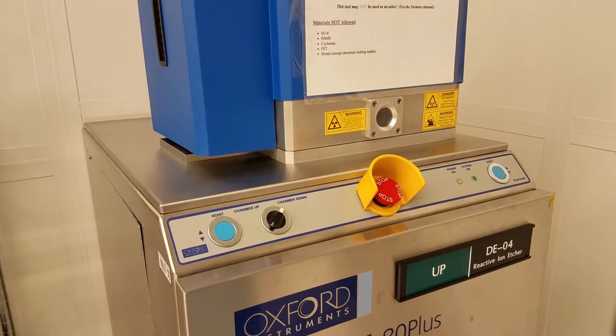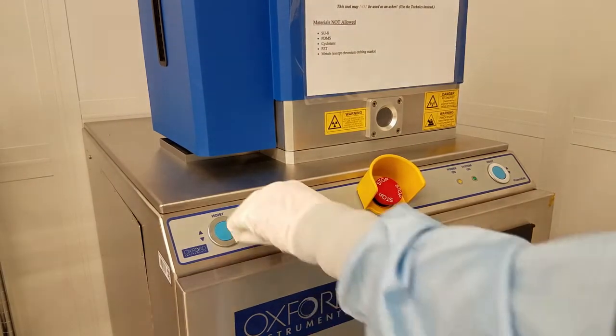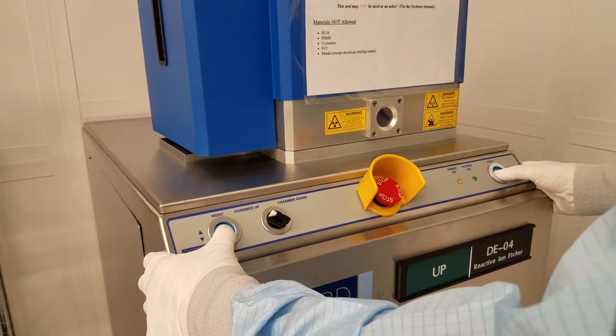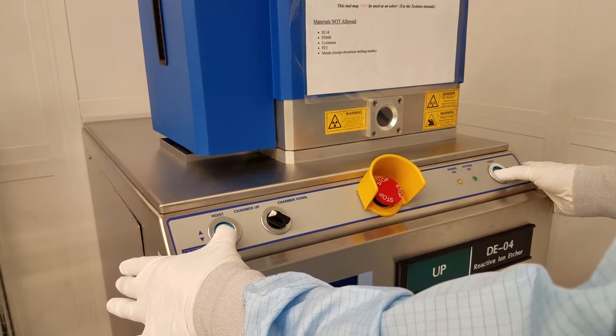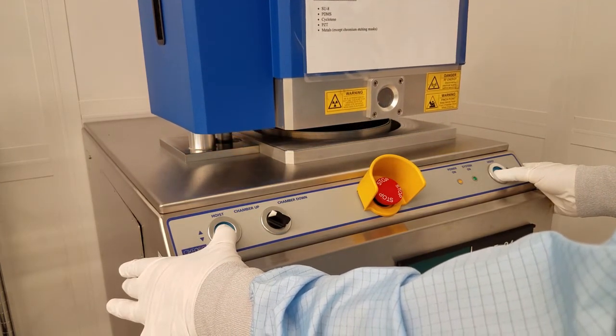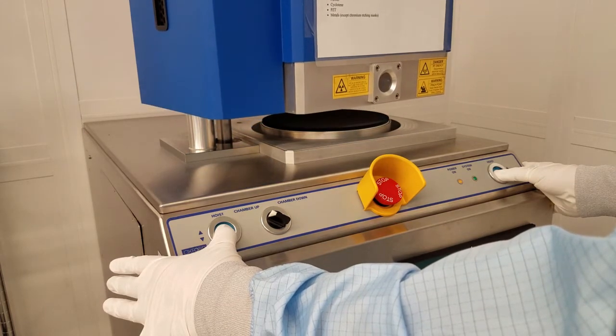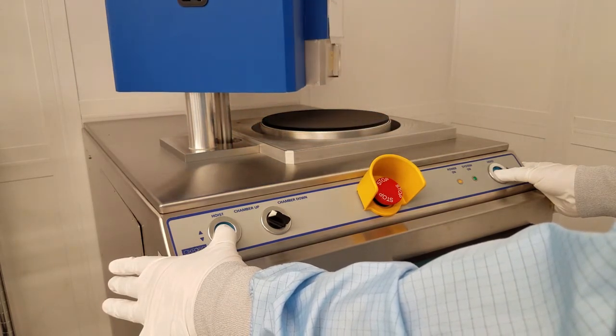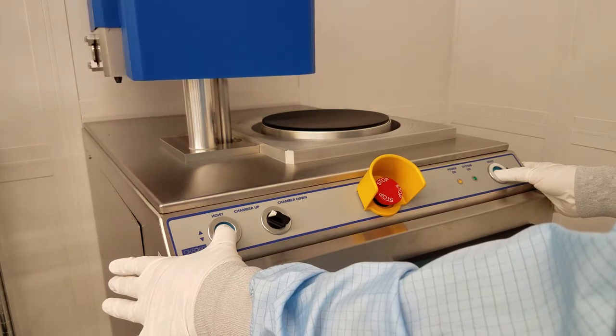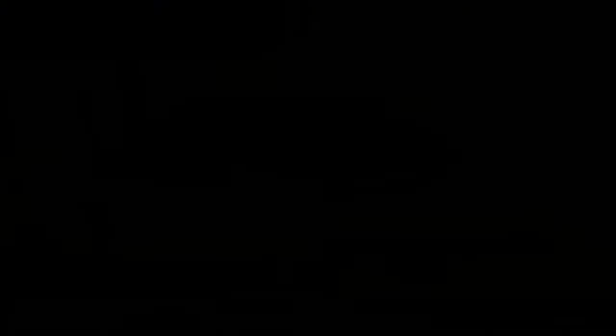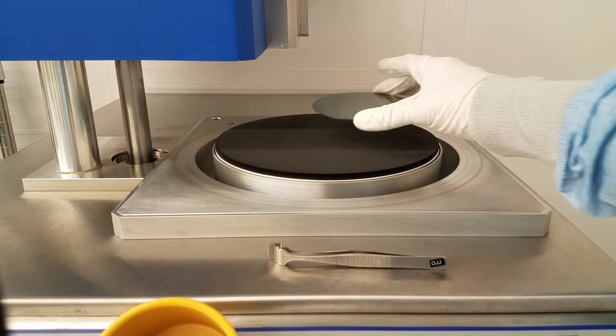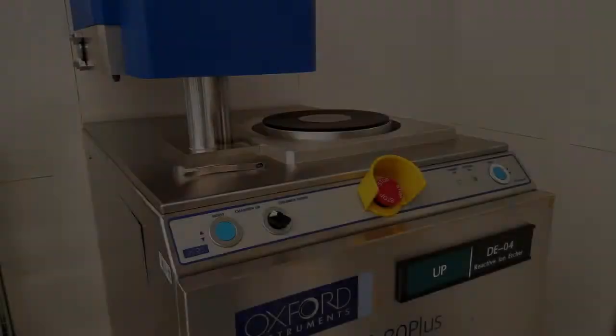Now that the chamber is vented, we can load our sample. Flip this switch and hold these two hoist buttons. Load your sample and lower the chamber.